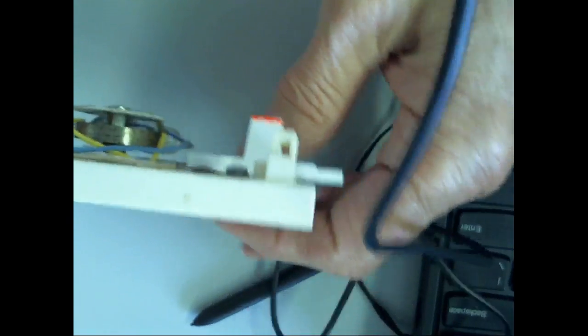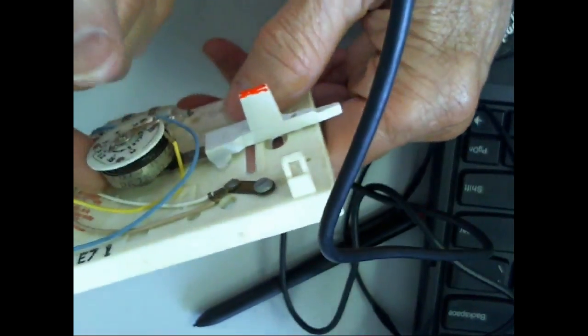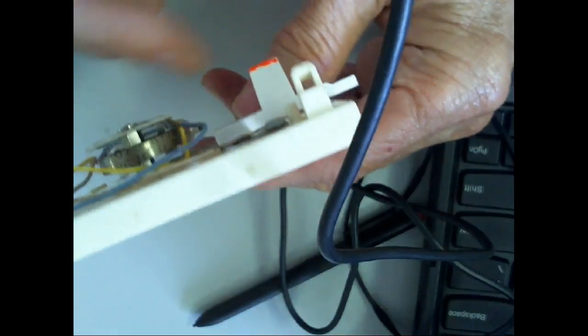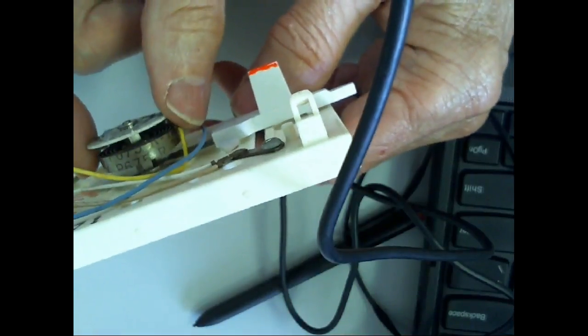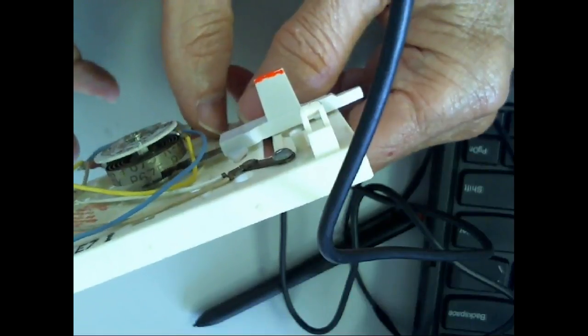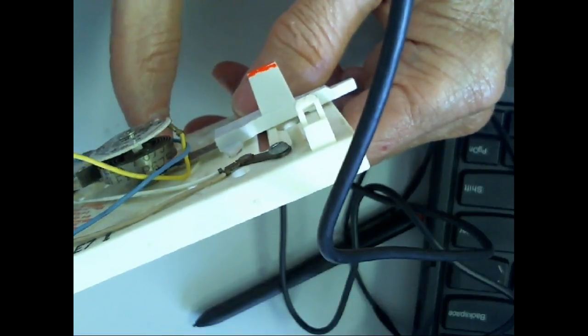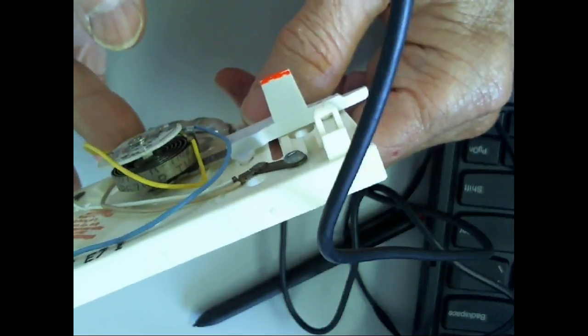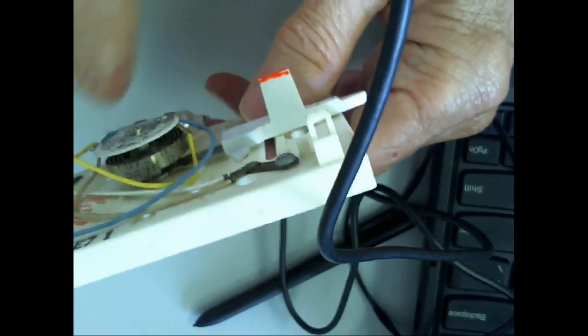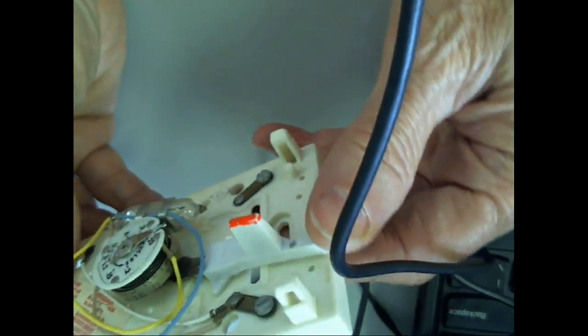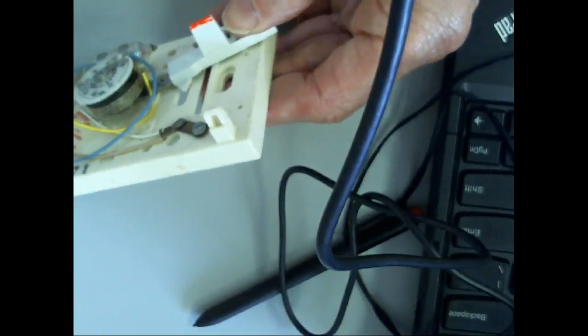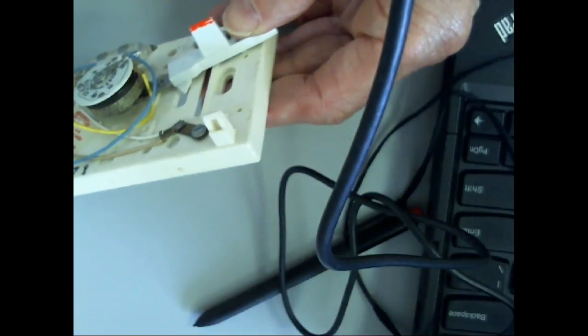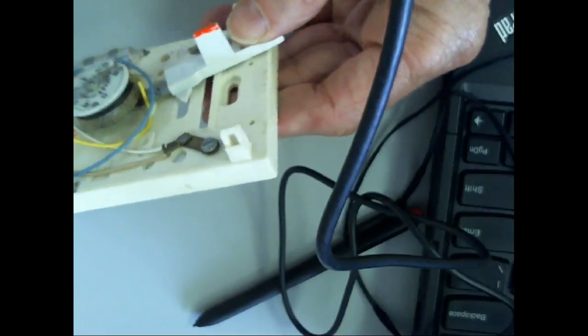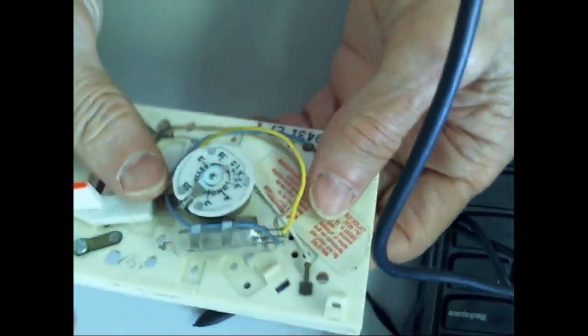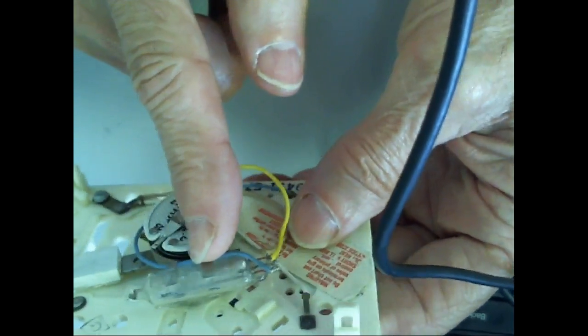So in the old days, what they did is they used a bimetallic strip right here, and it's in a coil. So what happens is when we heat it up, it's going to expand. It would try to cause the coil to unwind. If we cool it down, it would cause it to do what? It would cause it to contract. So what we could do is we could use that. And what we're doing right here is we're changing the spring tension on what's keeping it in the spiral or letting it come loose, right? You understand?